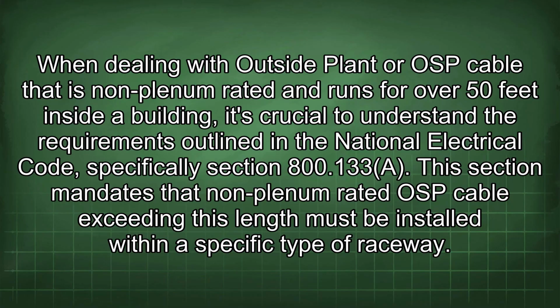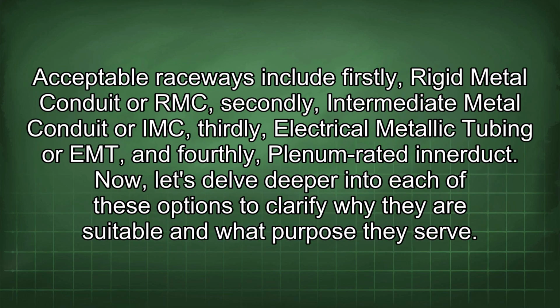When dealing with outside plant or OSP cable that is non-plenum rated and runs for over 50 feet inside a building, it's crucial to understand the requirements outlined in the National Electrical Code, specifically Section 800.133(A). This section mandates that non-plenum rated OSP cable exceeding this length must be installed within a specific type of raceway. Acceptable raceways include, firstly, rigid metal conduit or RMC, secondly, intermediate metal conduit or IMC, thirdly, electrical metallic tubing or EMT, and fourthly, plenum rated innerduct.